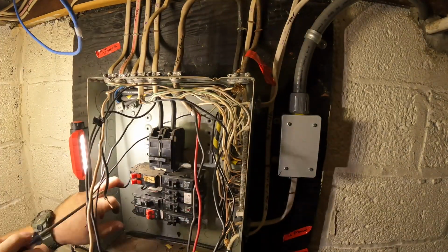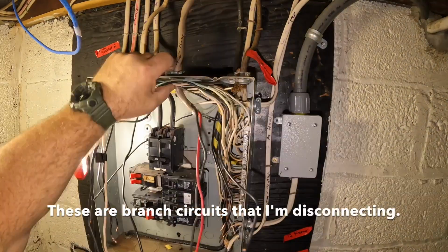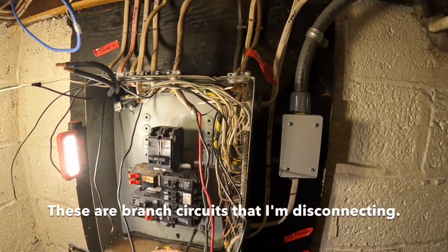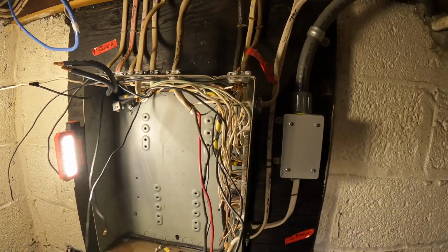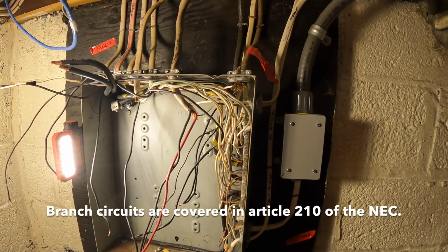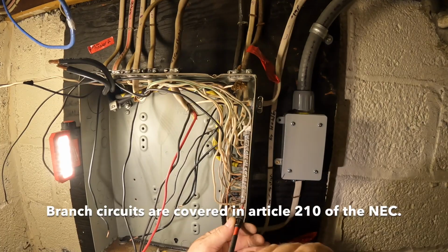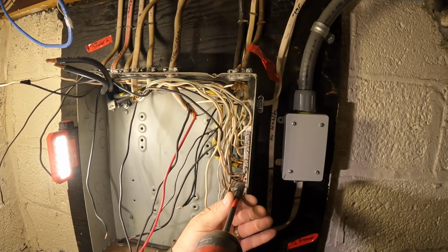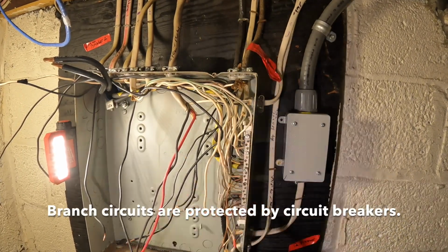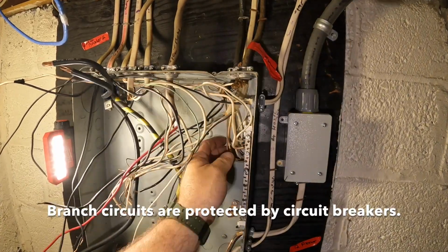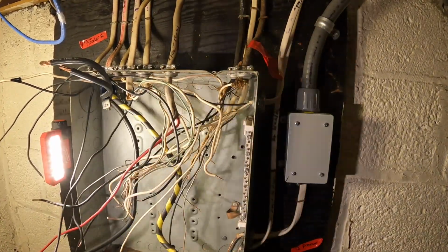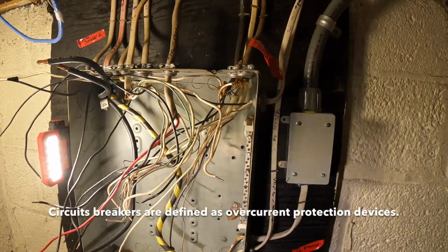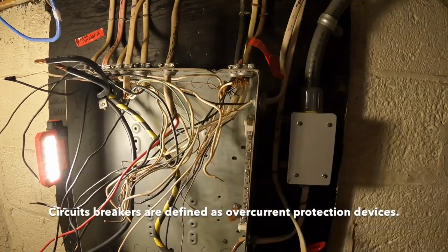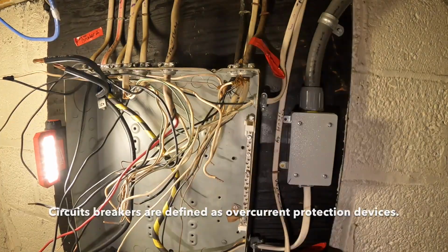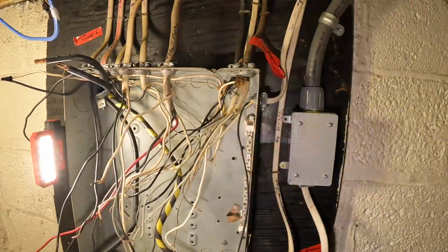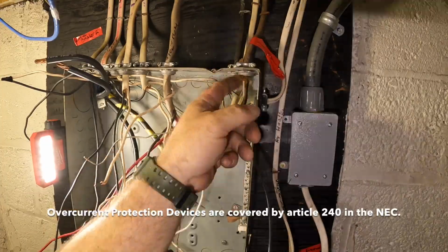So as with most panel upgrades or service upgrades, the first thing you want to do obviously is shed the load, which means turning off all of the electrical circuits in this panel here before you pull the meter on the outside. Now sometimes in this area, PSE&G, most of the time they have their circuit breakers locked. They have their meters locked. This particular meter was unlocked, and so I was able to access the meter without having to call PSE&G out first. Of course, I could have done that.